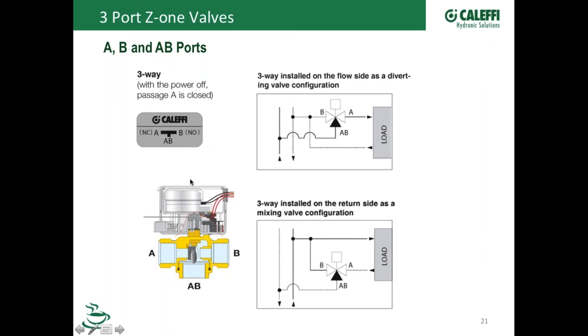So most of these are being shipped with normally closed actuators, and say they get piped wrong, you can switch them around. I really would recommend just repiping it for the long haul, because in a lot of cases, with most residential wholesale houses and whatnot, they're not going to stock normally open actuators because they're just not terribly common in the residential industry. Commercial is a different story. But if it does get piped backwards, you don't have to sweat it too much. You can put a normally open actuator on there and it will function. But you just have to be careful which side gets piped where.